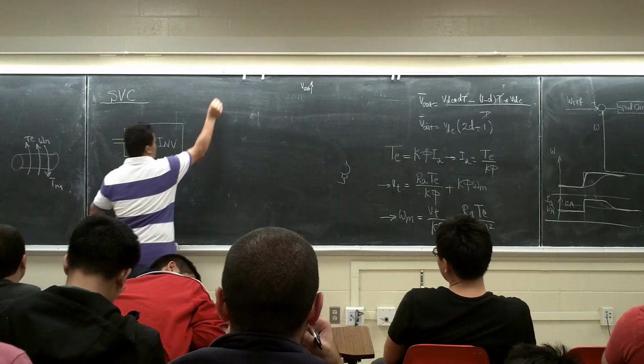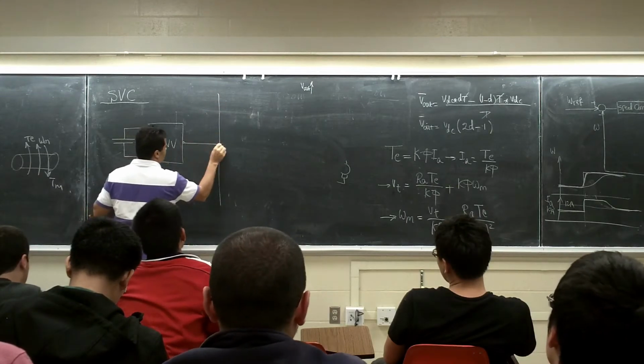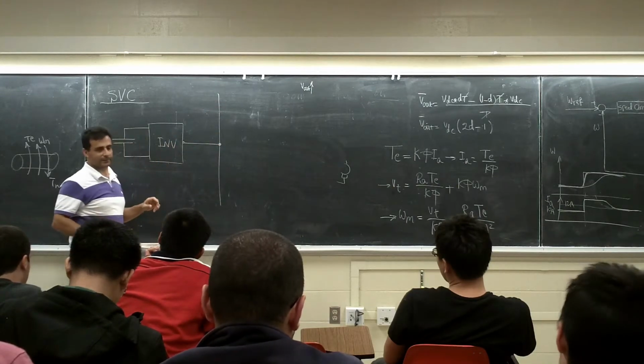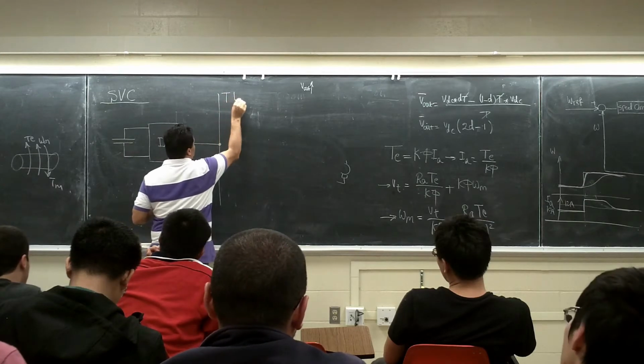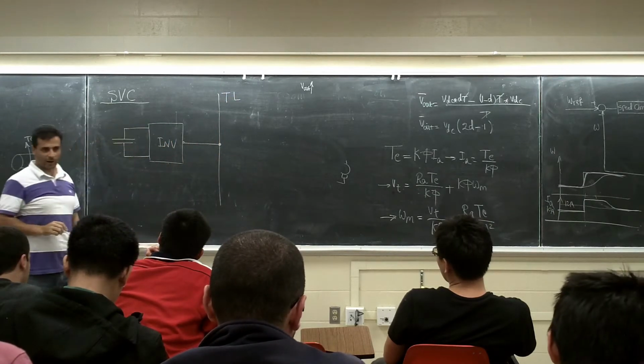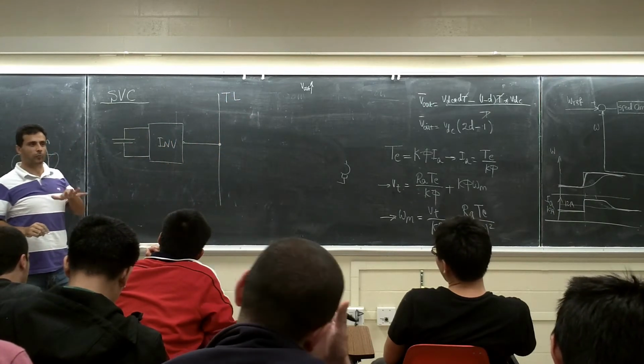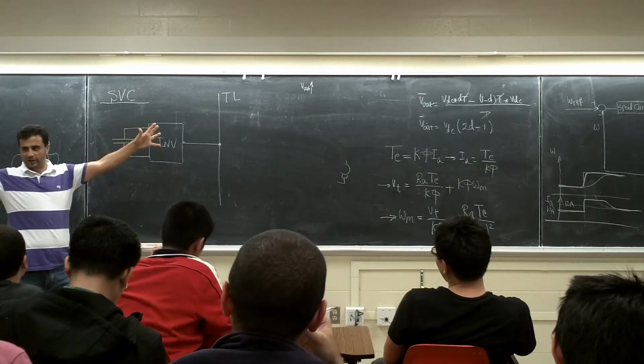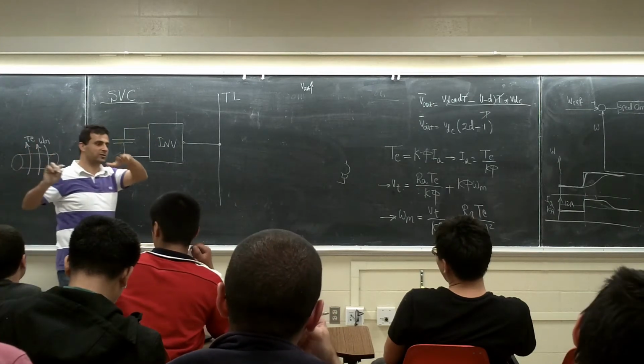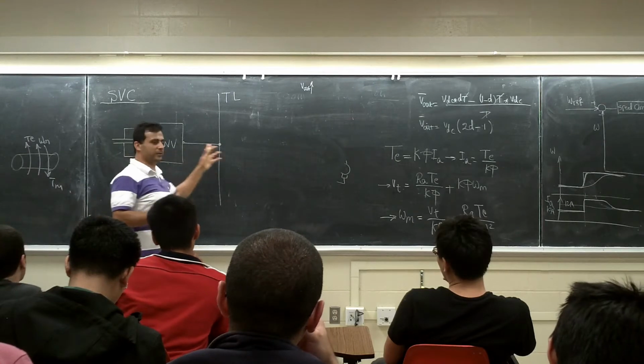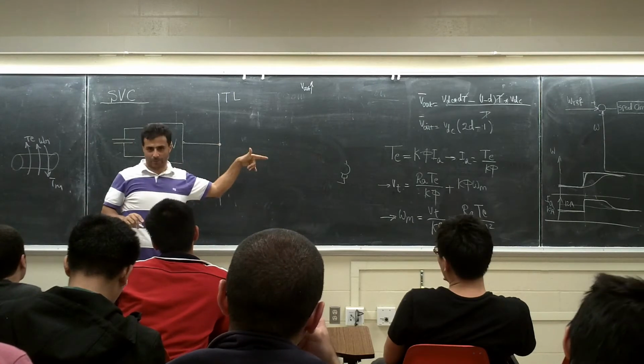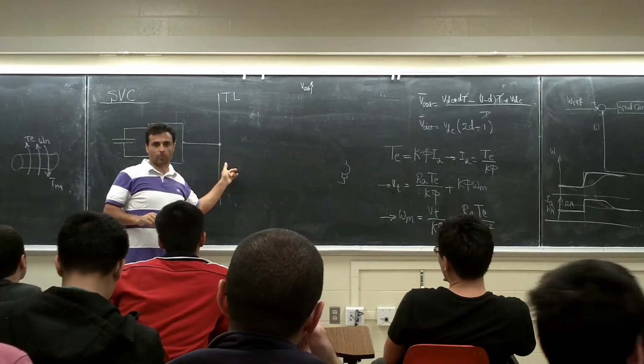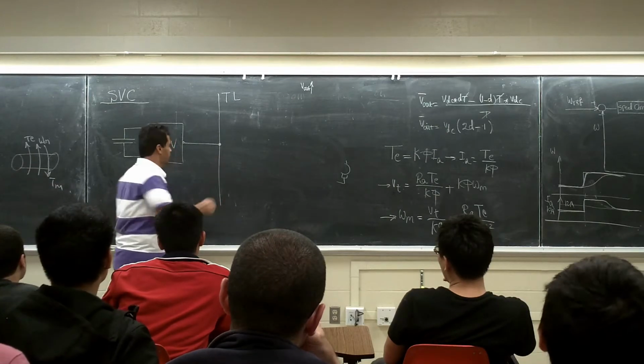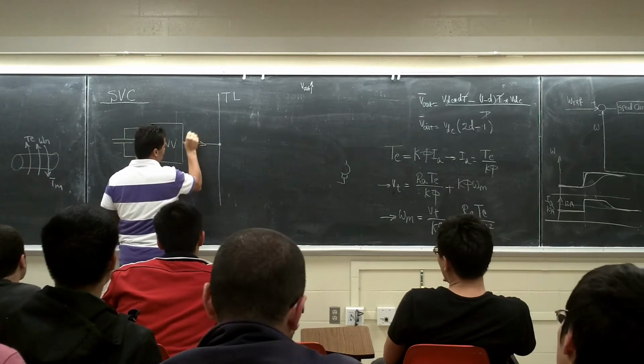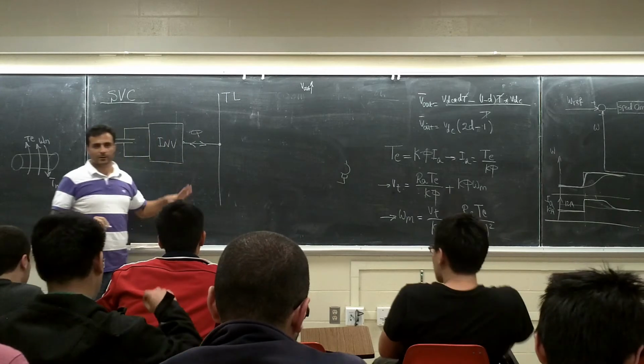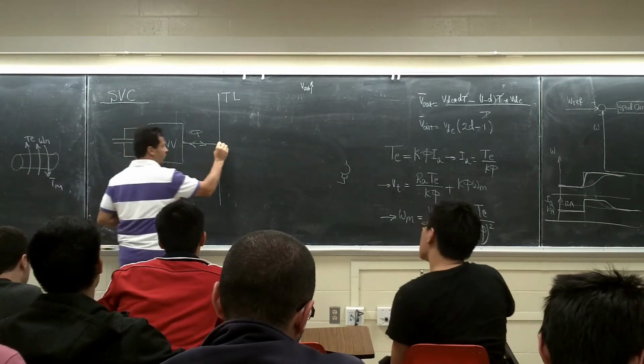You have your transmission line here, and this one is connected here - this is a transmission line or distribution grid. You want to stabilize your voltage. When you have a big grid, maybe at some points the voltage is too low. If you put one of these here, it can inject reactive power to the grid and support, they call it voltage support. This one can inject or absorb Q to the system, and it's going to support the voltage here.